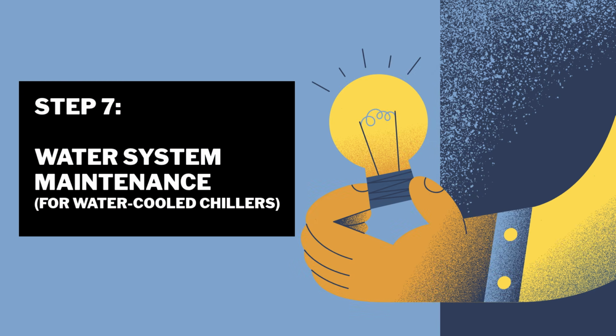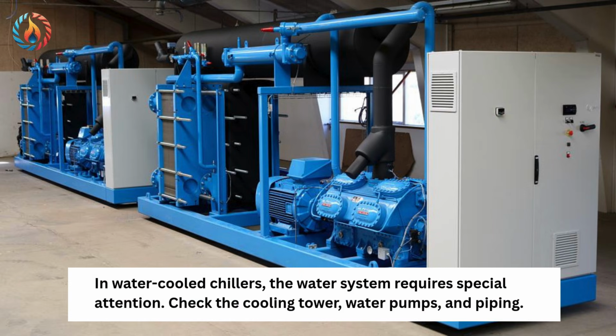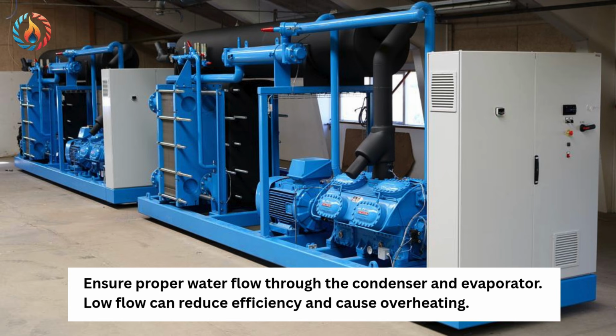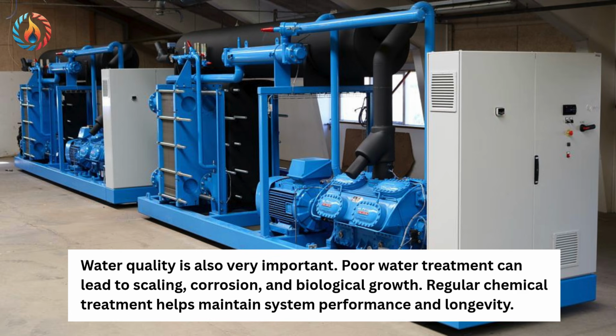Step 7. Water system maintenance for water-cooled chillers. In water-cooled chillers, the water system requires special attention. Check the cooling tower, water pumps, and piping. Ensure proper water flow through the condenser and evaporator. Low flow can reduce efficiency and cause overheating. Water quality is also very important. Poor water treatment can lead to scaling, corrosion, and biological growth. Regular chemical treatment helps maintain system performance and longevity.